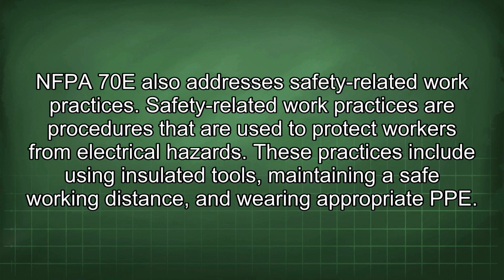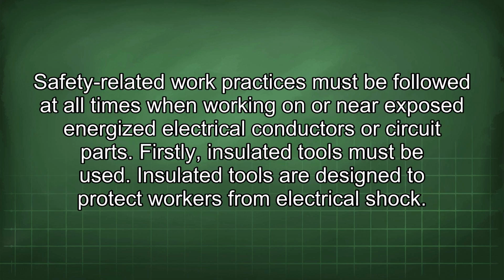NFPA 70E also addresses safety-related work practices. Safety-related work practices are procedures that are used to protect workers from electrical hazards. These practices include using insulated tools, maintaining a safe working distance, and wearing appropriate PPE. Safety-related work practices must be followed at all times when working on or near exposed energized electrical conductors or circuit parts.